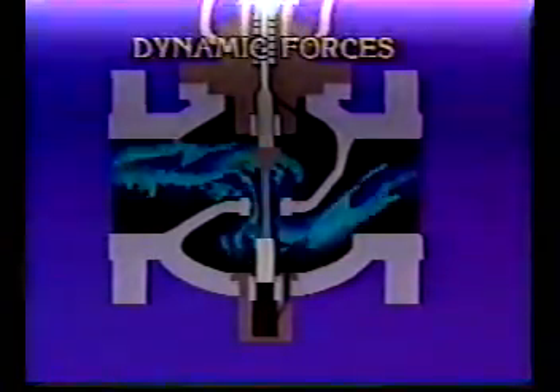Now, let's look at what happens to forces as a valve opens and fluid begins to flow. These are the dynamic forces and can be extremely complex. We'll use a graph to illustrate how these forces can vary as valve opening increases. This plot represents the dynamic force on the plug in a quick opening globe valve when flow is tending to open the valve. As you can see, the force varies with the amount of flow through the valve.